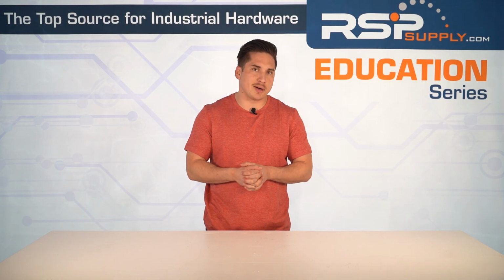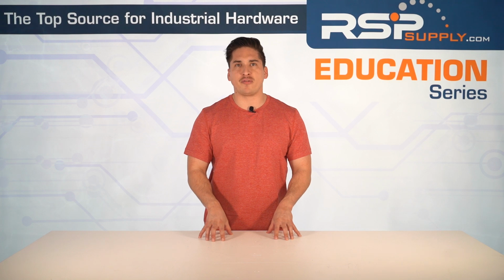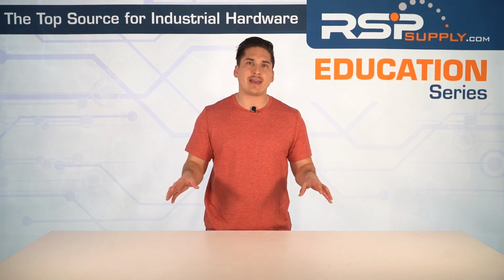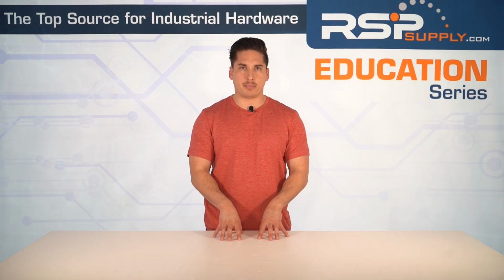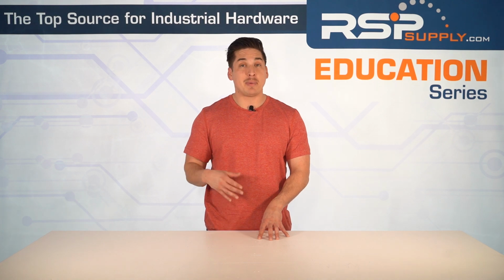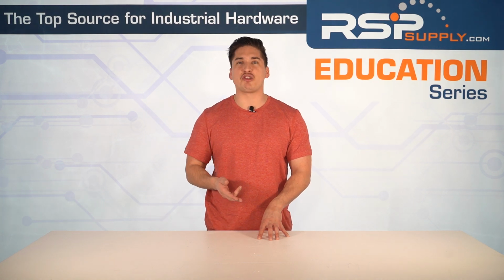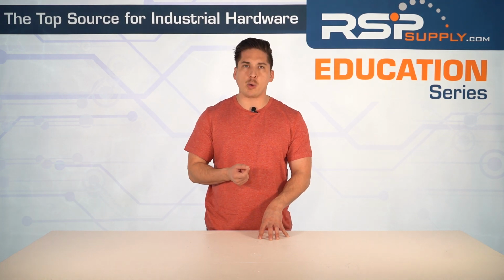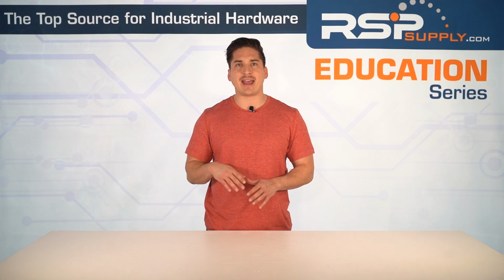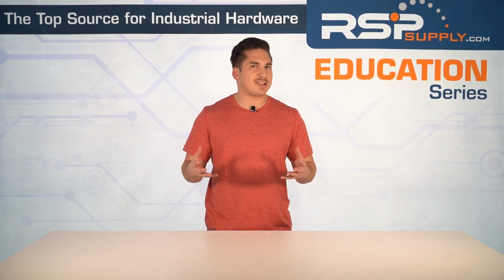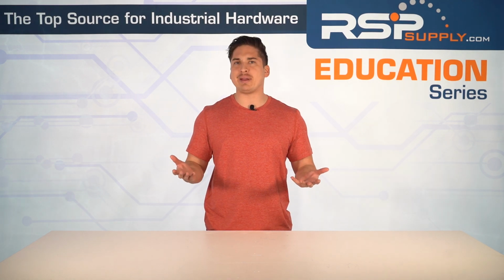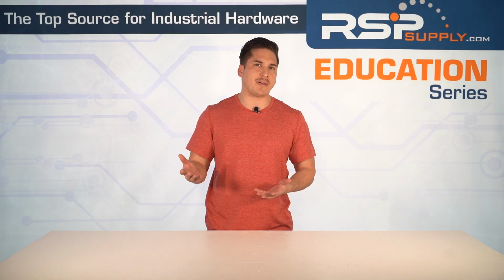In industrial settings where thousands of amps flow through switchboards, a simple breaker just won't cut it. You need a solution that not only interrupts faults, but also safely handles high energy arcs. That's where air circuit breakers, or ACBs, come in. Meet the air circuit breaker. It's the heavyweight champion of power distribution protection. These breakers don't just switch off power, they extinguish high energy arcs using air, magnetic blowouts, and advanced cooling systems. But how does this all work? Why are ACBs essential in industries handling thousands of amps?